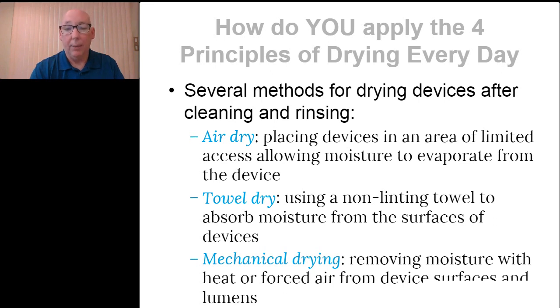Mechanical drying, such as drying cabinets, can certainly speed up the process and provides uniform heating and drying, hence inhibiting bacterial recontamination. Drying cabinets do come at a cost though, right? Dollars in real estate. They're going to cost money and they're going to take up space, but usually an excellent cost-effective investment to render devices dry. So some of you may be air drying devices. There are advantages and disadvantages with that. Towel drying, again, always using a non-lint towel to absorb moisture from the surface of devices, certainly the exterior of a device. And the mechanical drying typically comes in the form of drying cabinets.